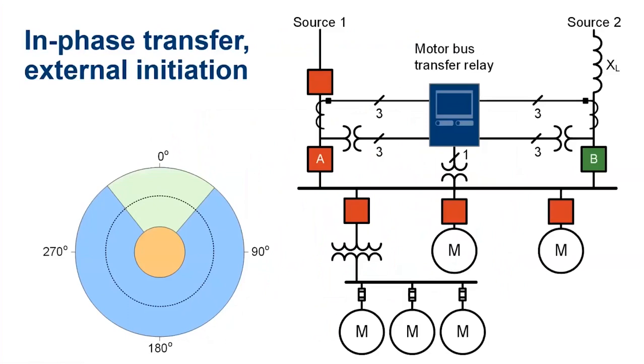Okay, so now we're going to talk a little bit about the in-phase transfer. It will typically take longer to determine that we can do an in-phase transfer than a fast one, because the fast transfer is just a quick phase check, which verifies that the phase now is within boundary. We understand that as within 30 degrees of what it's supposed to be on the other feeder, and that the magnitude is above a threshold. So those are quick checks.